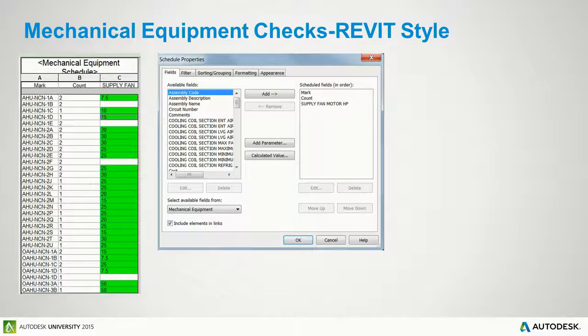And so the way that I check to make sure is I've got this count field right here. I should see a 2 in that count field if the mechanical model has that piece of equipment and I've made an effort to circuit that piece of equipment. I've acknowledged that it's there. If it only has a 1, then I need to figure out either the mechanical team deleted it or I have not recognized in my model with my connector symbol that it's there.